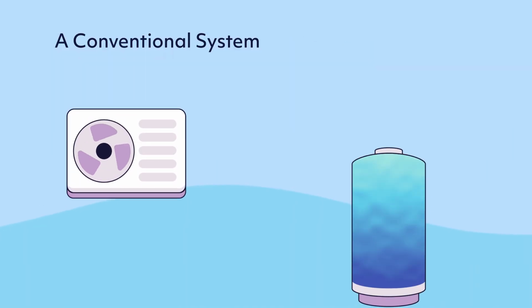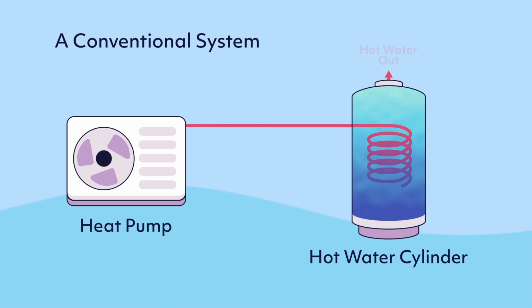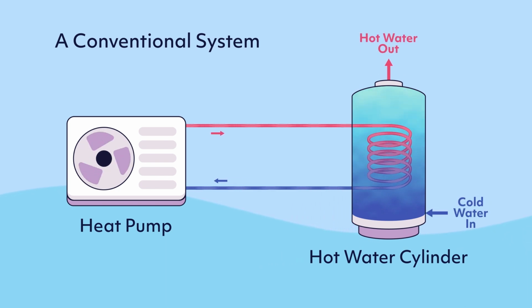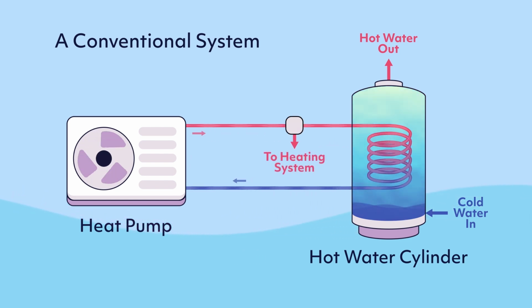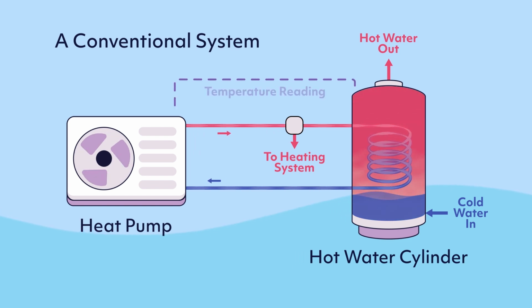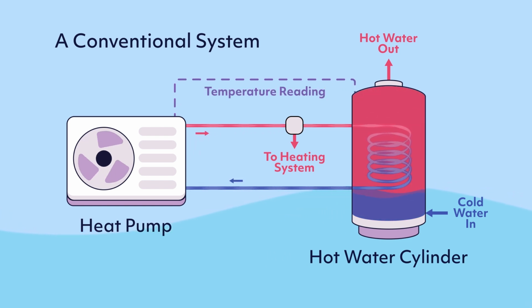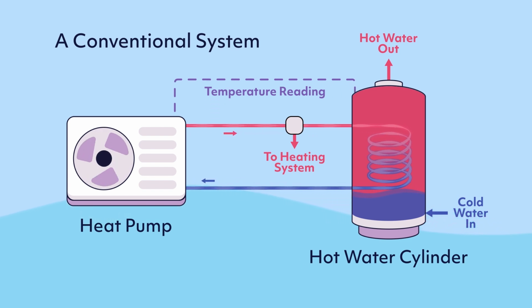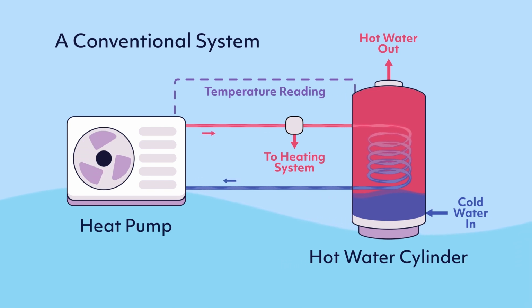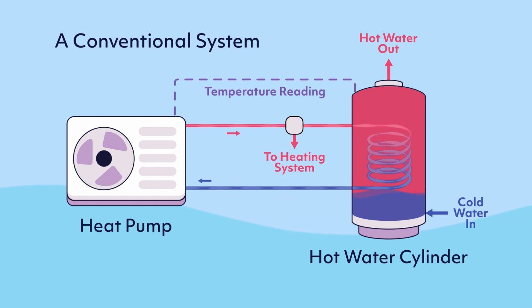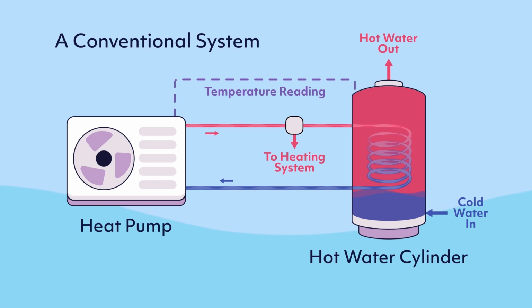Most conventional heat pump systems transfer thermal energy through an indirect coil inside the hot water cylinder. The heat travels through the water in the system loop, which also circulates around the rest of the central heating system. A probe inside the cylinder measures the hot water temperature, and whenever this drops below the set point, the heat pump starts transferring energy to the coil. Most systems will prioritize the hot water cylinder by switching the diverter valve to call for heat.